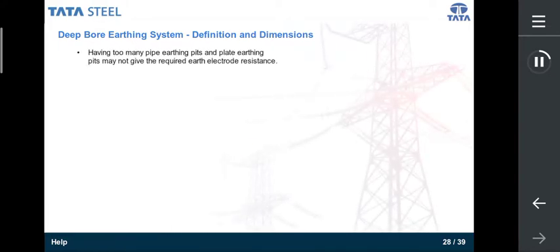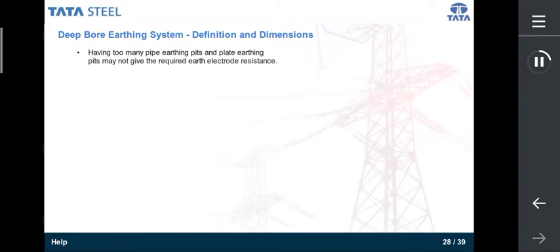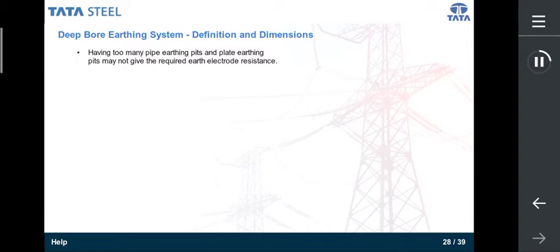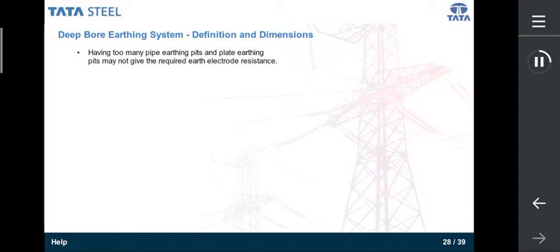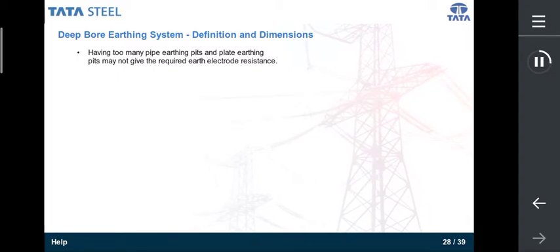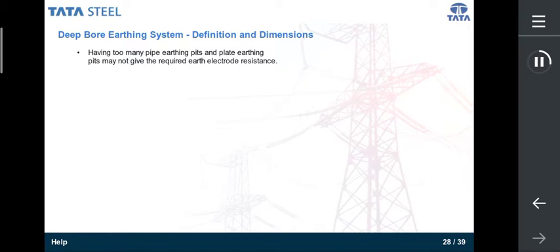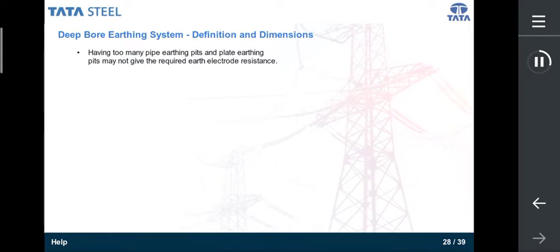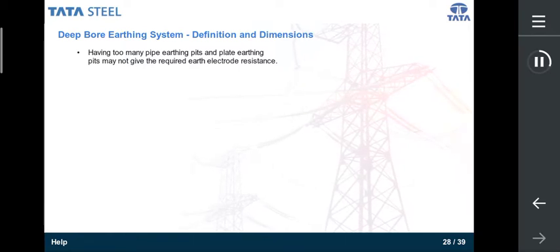Having too many pipe earthing pits and plate earthing pits may not give the required earth electrode resistance. Further, it is not feasible to have multiple earthing pits at one place since the area has to accommodate other equipments also.